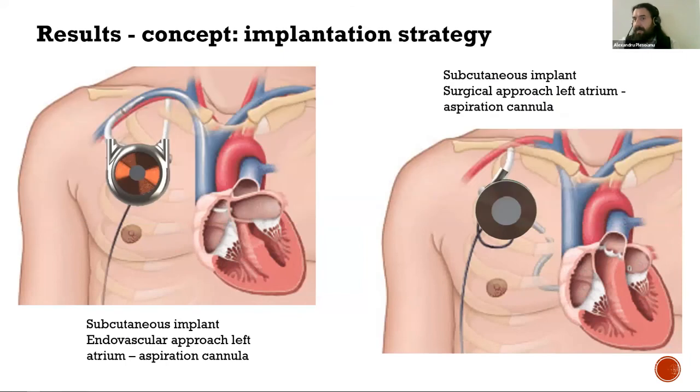We have created a left ventricular assist device for partial support for patients with New York Heart Association class 3-4 heart failure that might pump up to 5 liters per minute of blood from the left side of the heart to the arterial system at a differential pressure of 100 millimeters mercury. The characteristics of the device, the actors, and the interfaces involved were defined. The ventricular assist device contains an implant, a controller, rechargeable batteries, a charging station, and the console.